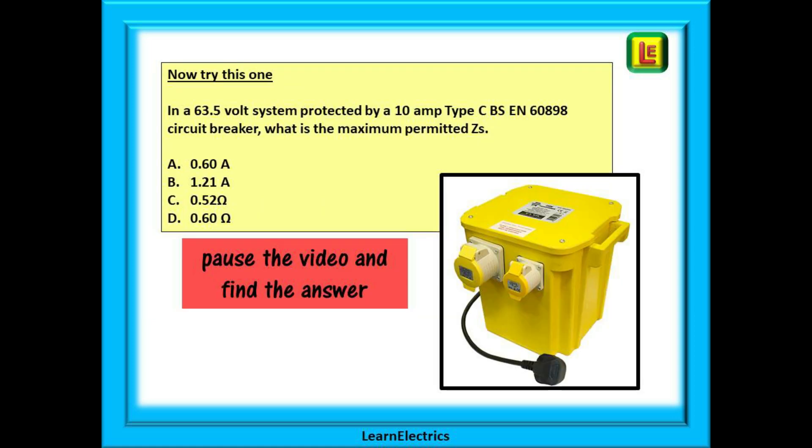Now try this one. If a 63.5 volt system is protected by a 10 amp type C BS EN 60898 circuit breaker, what is the maximum permitted ZS? You need to pick out the key words, the clues to finding the answer. 63.5 volts implies reduced low voltage. ZS implies start at page 65 and flick just 5 pages to find table 41.6 on page 74. We have 4 multiple choice answers as shown. Pause the video and have a go at answering the question.